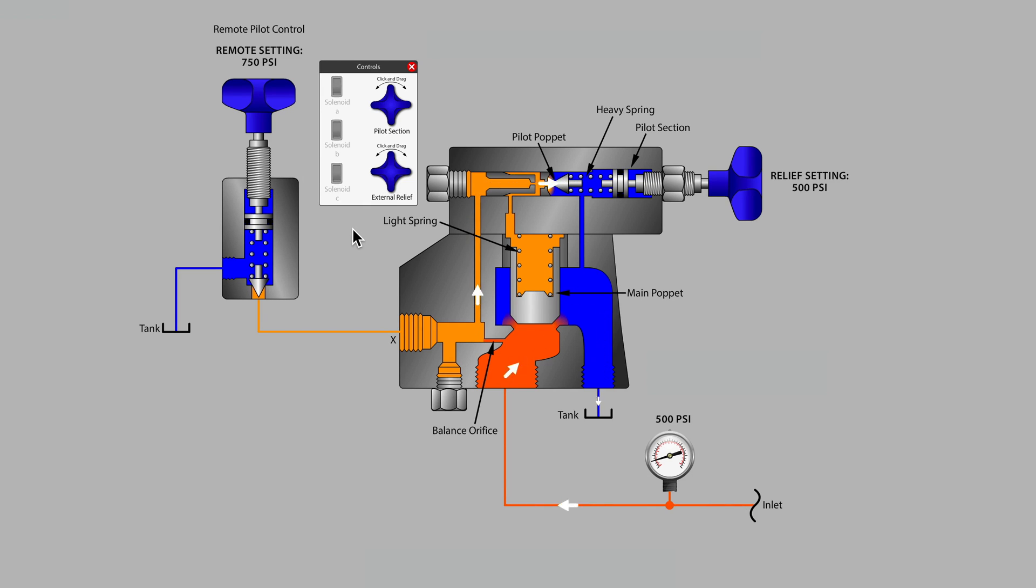We covered the main type of relief valve you see here in an earlier video. In this particular case we have essentially two pilot sections: the main pilot section that is bolted to the relief valve controlling the main relief poppet, and then at a distance, perhaps on an operator's console via port X, sometimes known as the vent port, we have a long hydraulic hose going to another small pilot section.